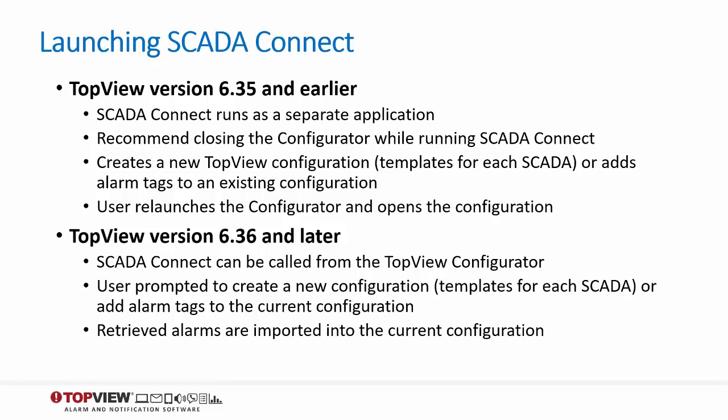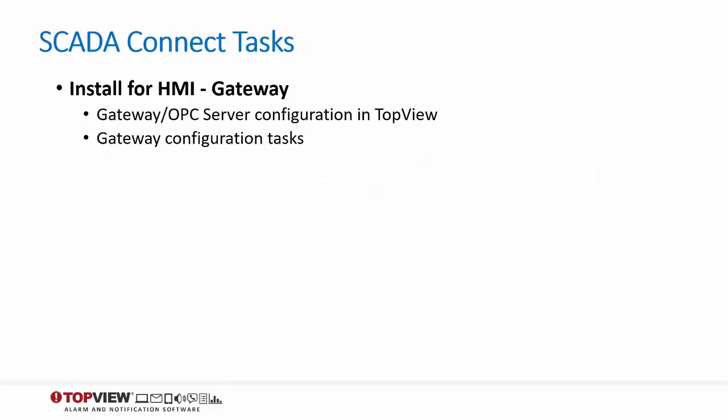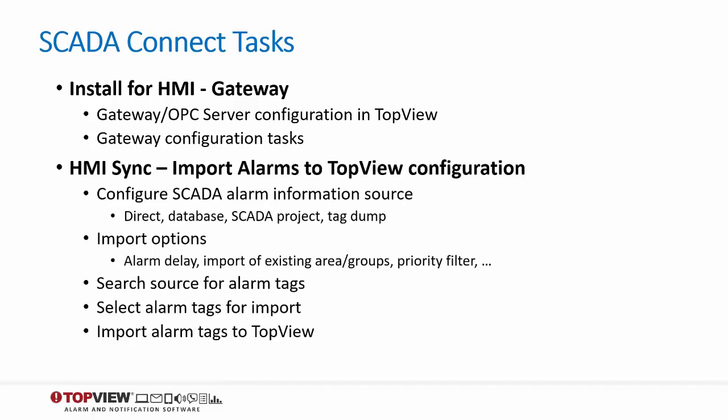The retrieved alarms are then imported into the configuration. The first task for the SCADA Connect user is to configure the gateway. This involves the configuration of the gateway server in Top View and may, depending on the SCADA, involve configuration steps of the gateway itself. Most users will only perform this step once. Once the gateway is configured, HMISync will be used to import alarms from the SCADA to a Top View configuration. Each SCADA alarm database is accessed in a specific way. Depending on the SCADA, this may be a direct connection to the SCADA runtime, accessing the SCADA alarm database or project, or a tag database dump file, which is usually a CSV. After selecting the desired import options, the user will be presented with a list of discovered SCADA alarms. After selecting the desired alarms for import, SCADA Connect will import these alarms into the Top View configuration.